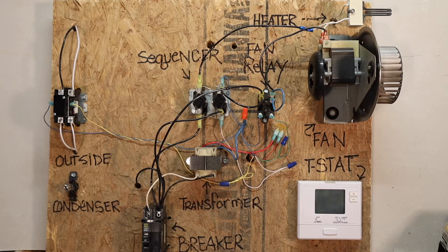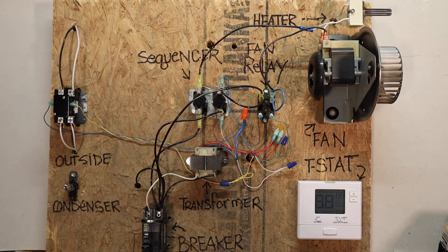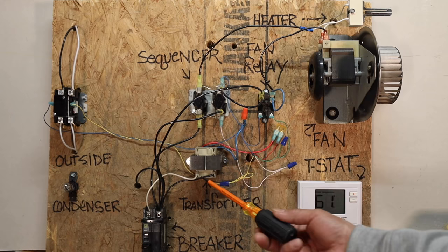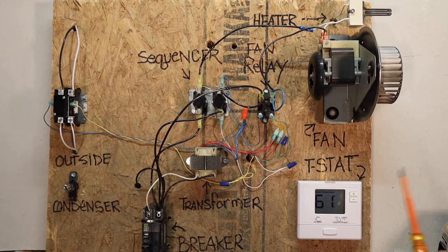Basically what's going on when you turn on the power: power from the main power supply is passing through the breaker and it's going into this transformer and being transformed to 24 volts, which is a small voltage so it can be used inside these little coils of the controls.